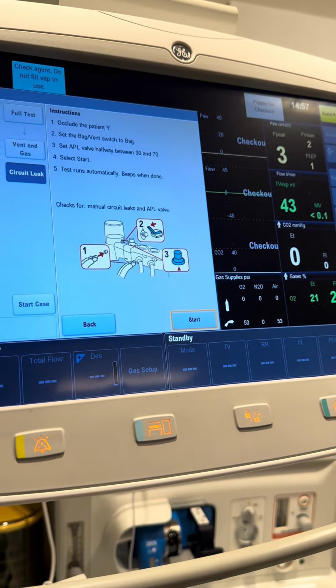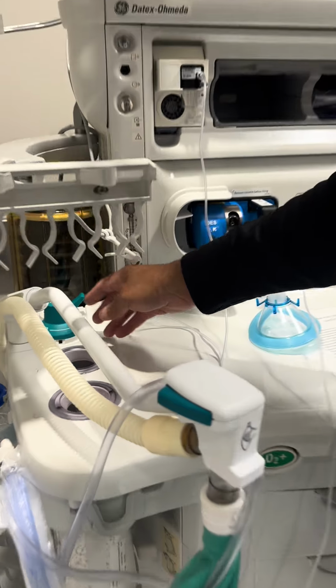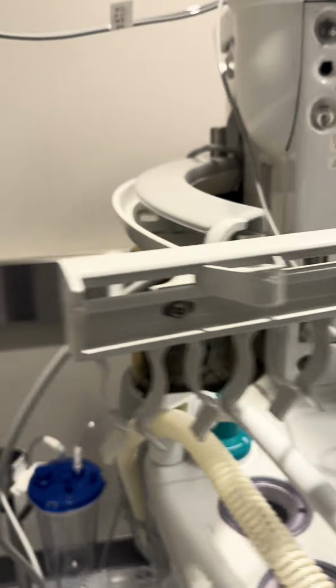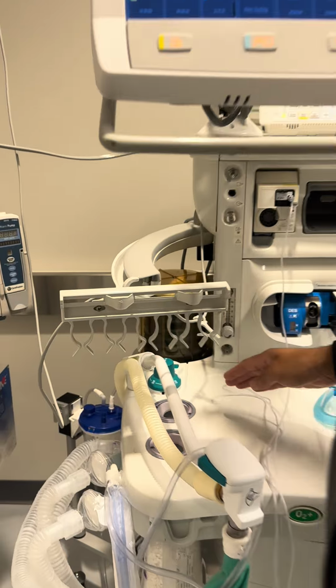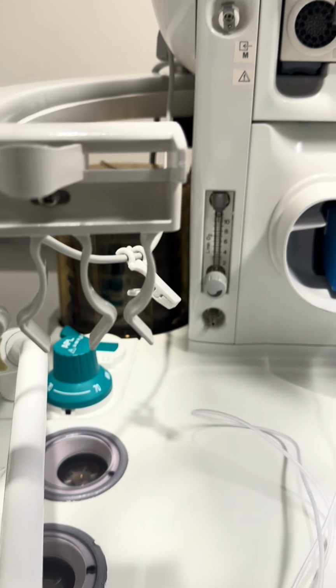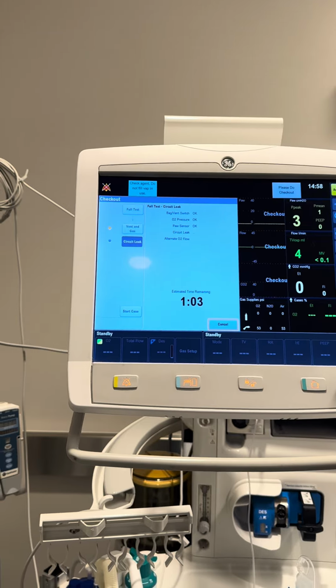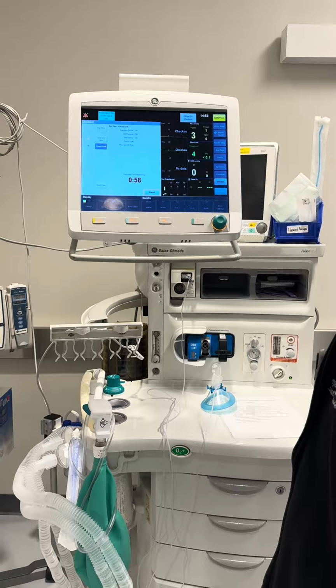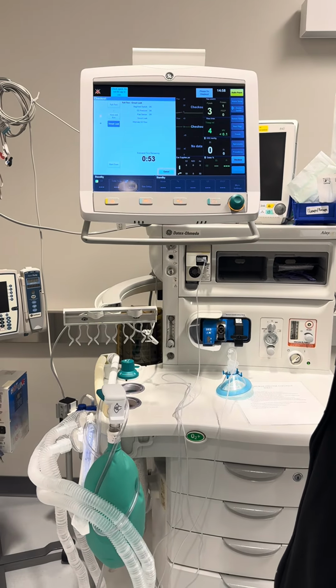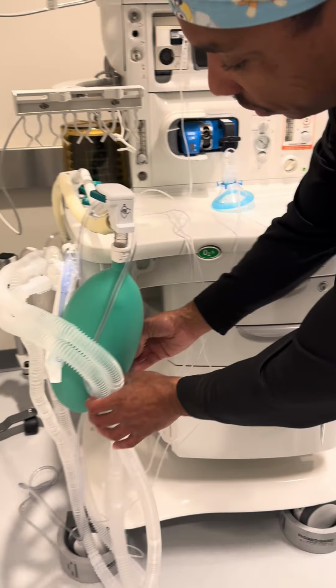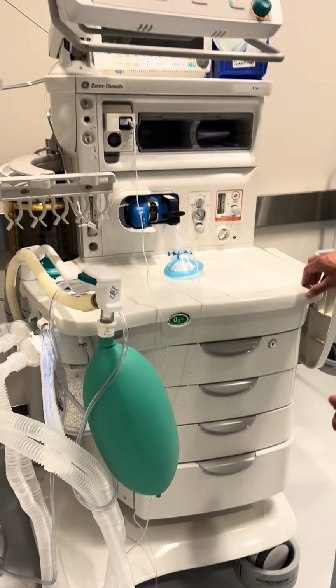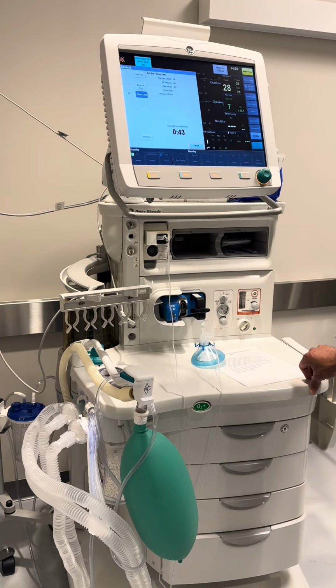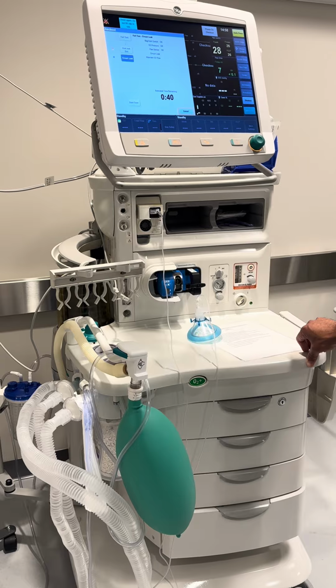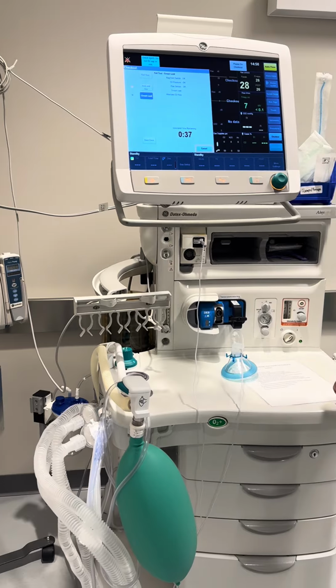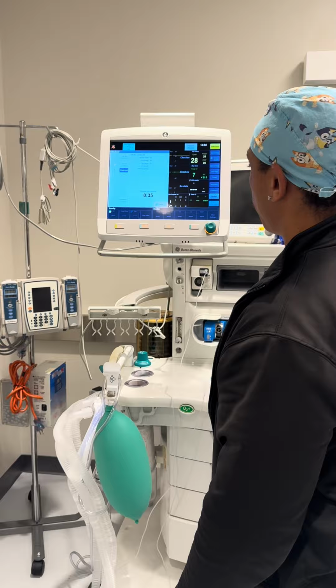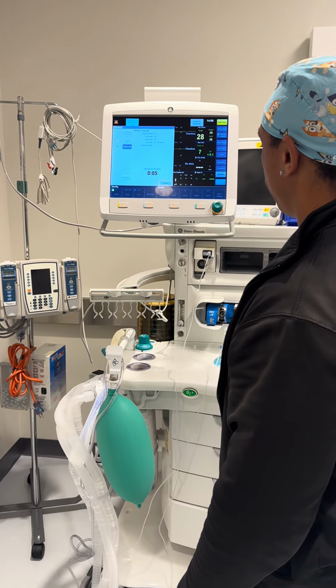So we're gonna hit accept, and then we're going to set our APL valve between 30 and 70, which is set now. And then we're going ahead and press start. Sorry about that. We're gonna go to bag, and then we're gonna press start. And you can see the bag getting bigger. So this is just verifying that there's no leak inside the actual circuit itself. So we're good to go there.